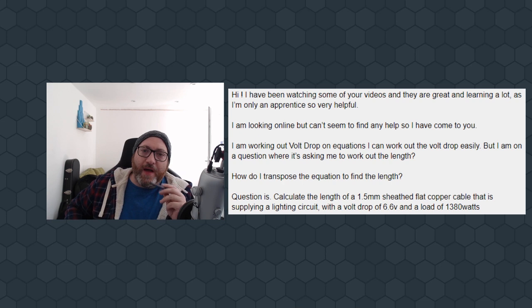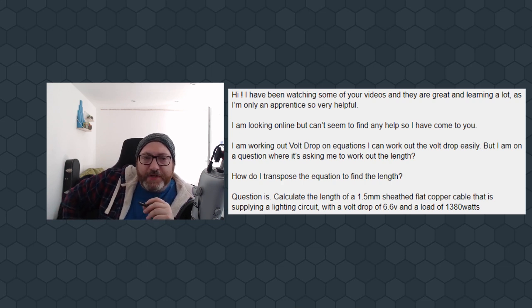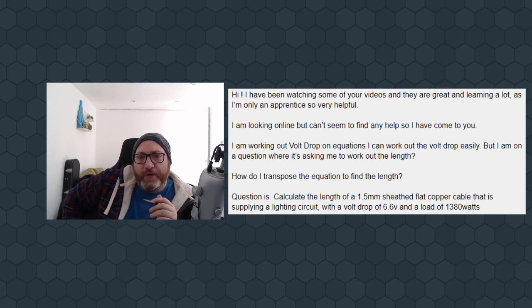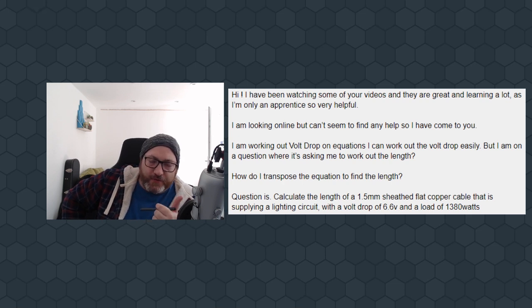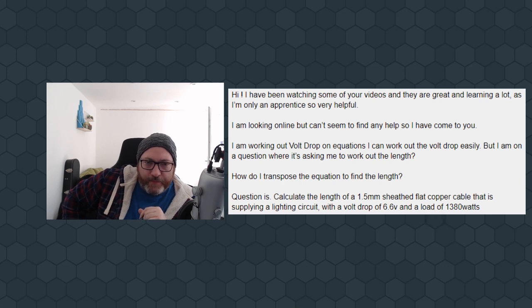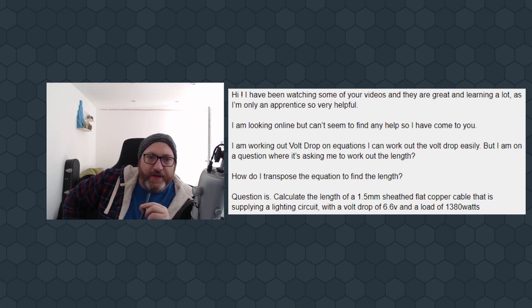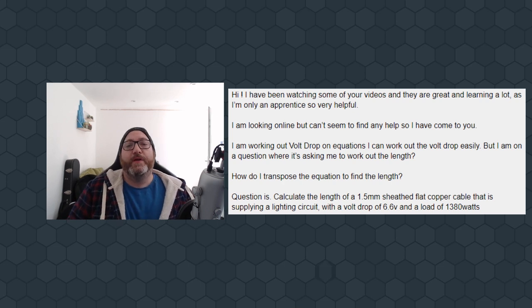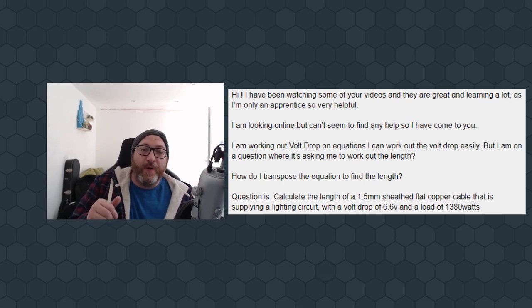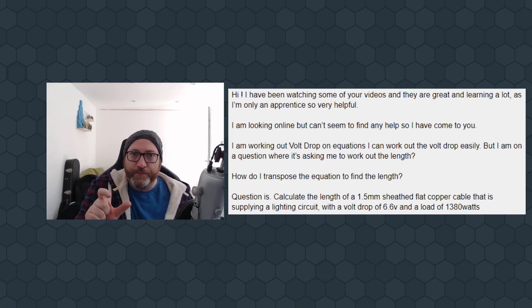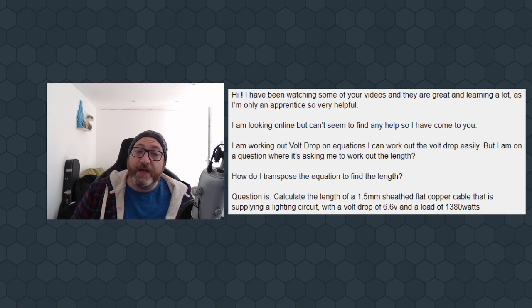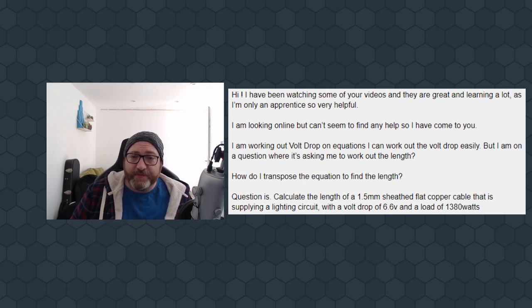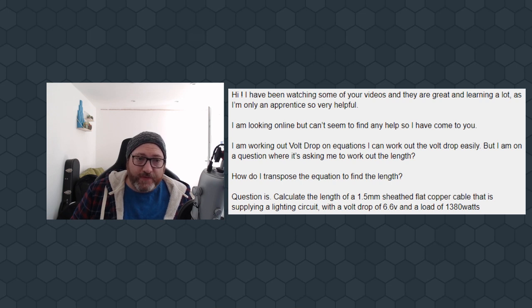I'm looking online, but I can't seem to find any help, so I've come to you. I'm working on a Volt Drop on equations. I can work out the Volt Drop easily, so we notice the Volt Drop formula, but I'm on a question where it's asking me to work out the length. How do I transpose the equation to find the length? The question is, calculate the length of a 1.5mm sheathed flat copper cable that's supplying a lighting circuit with a Volt Drop of 6.6 volts and a load of 1380 watts.